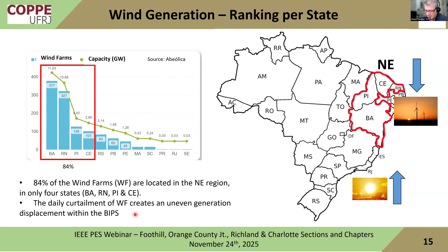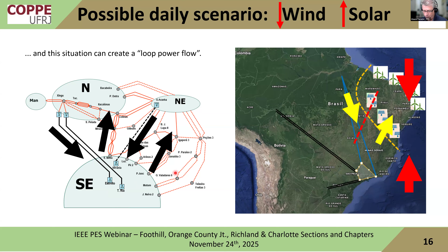So the daily curtailment of wind farms creates an uneven generation displacement within the system. It's not evenly distributed, which causes problems with HVDC lines, because this situation can create what we call loop flow — where DC links push power, say, from northeast to southeast, while the AC system pushes power the other way, creating a loop flow. And remember, we're talking about HVDC links spanning 2,000 to 2,500 kilometers, so it's a big loop flow.